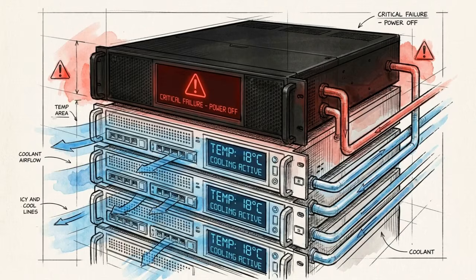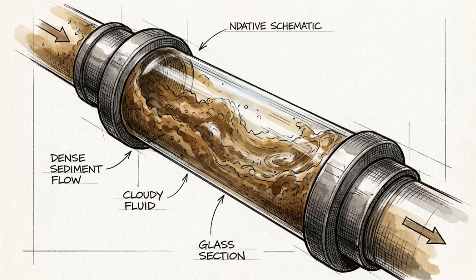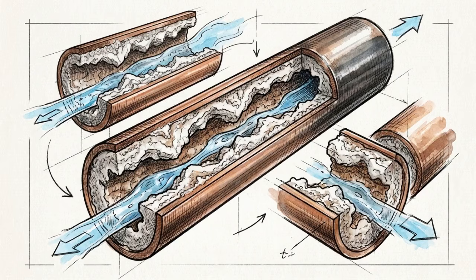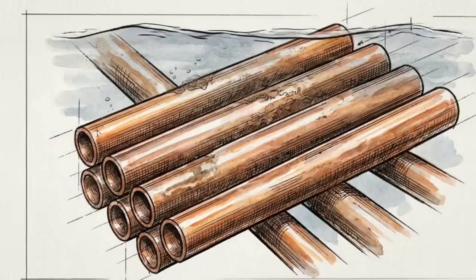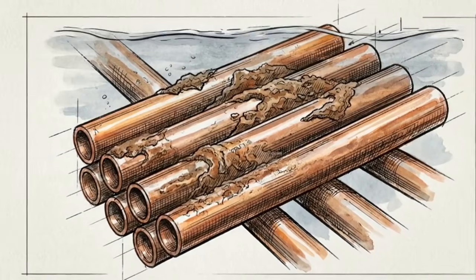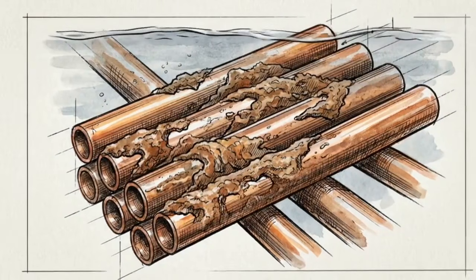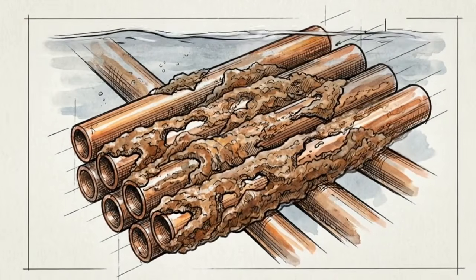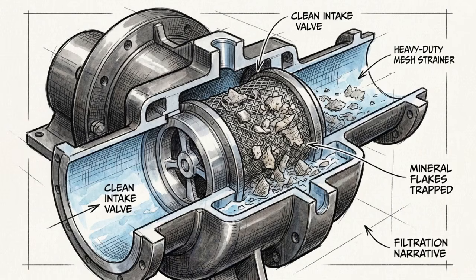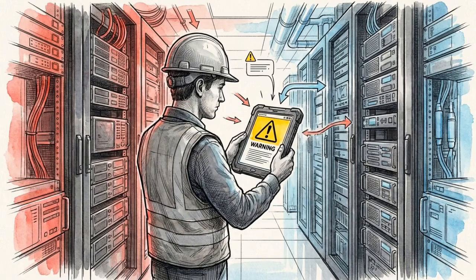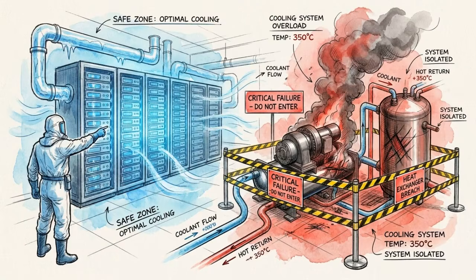A third major threat comes from rapid water quality events, where sudden particulate influx causes catastrophic fouling, severely altering the plant's heat exchange efficiency. Unchecked water chemistry will aggressively destroy high-performance mechanical equipment from the inside out. The emergency protocol requires halting makeup water loss immediately. This protects the pumps from net positive suction head cavitation and stops permanent scaling from baking into the chiller tubes. During complex cascading failures, emergency operating procedures share one primary directive: prioritize IT thermal stabilization and life safety over attempting to fix the broken machine on the fly.